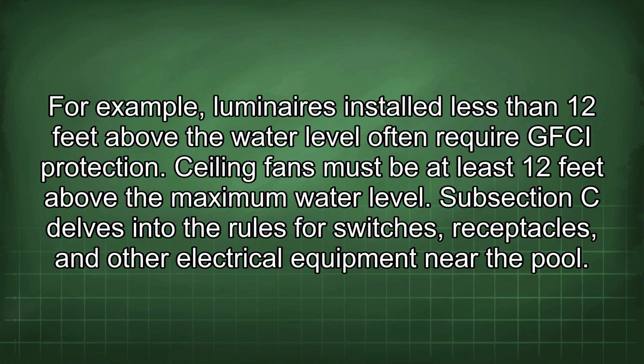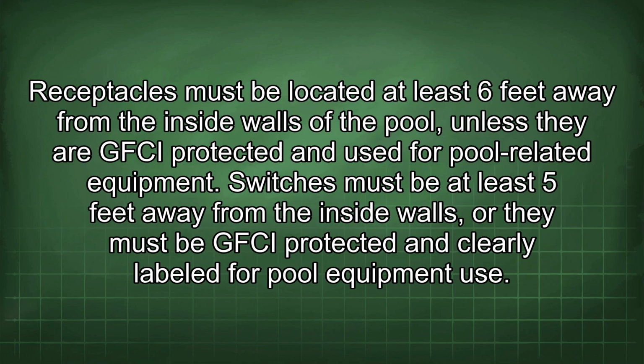Subsection C delves into the rules for switches, receptacles, and other electrical equipment near the pool. Receptacles must be located at least 6 feet away from the inside walls of the pool unless they are GFCI protected and used for pool-related equipment. Switches must be at least 5 feet away from the inside walls, or they must be GFCI protected and clearly labeled for pool equipment use.